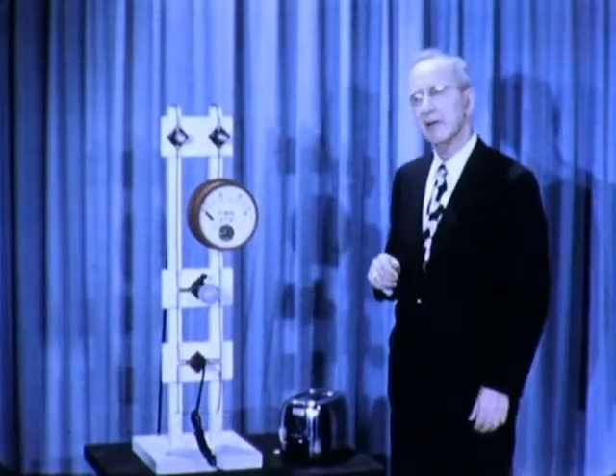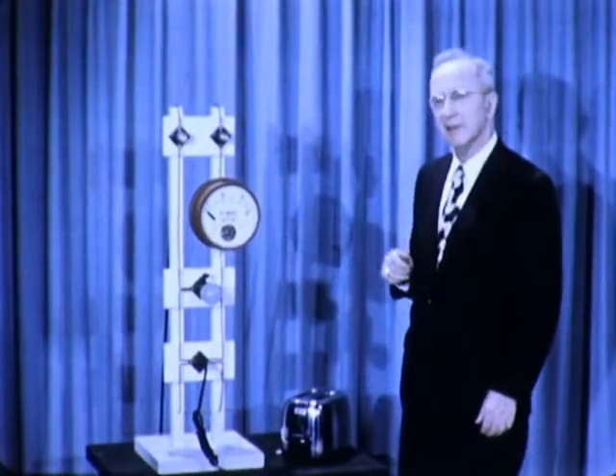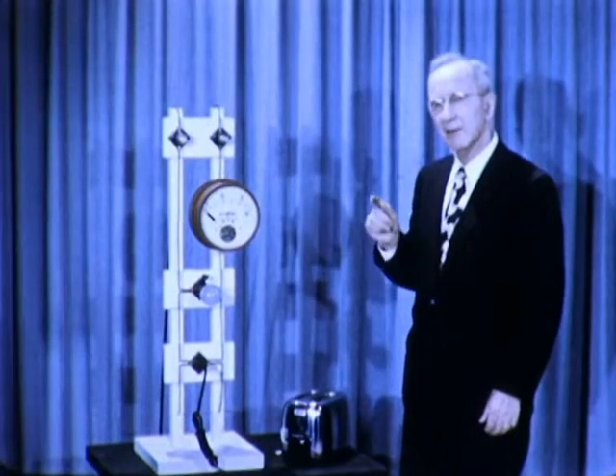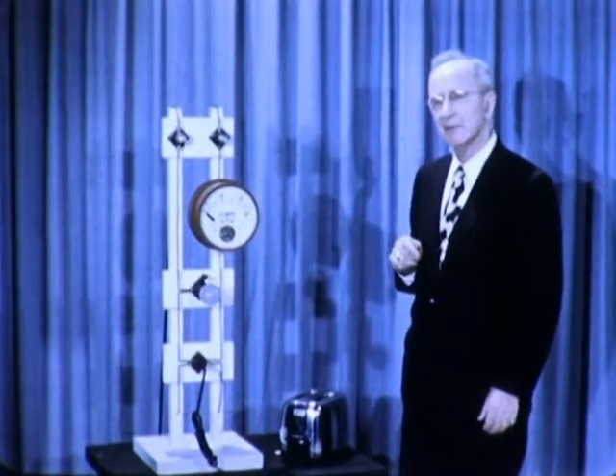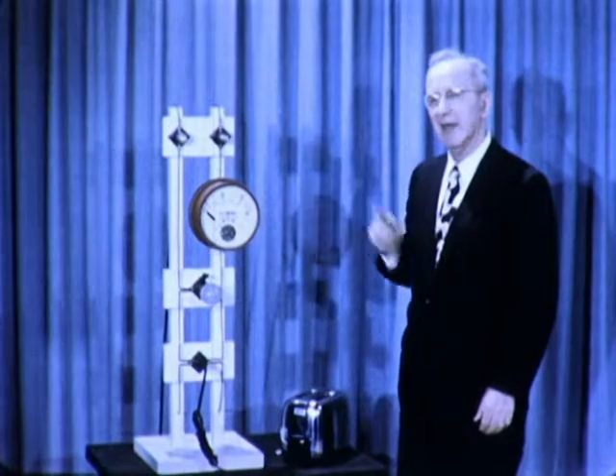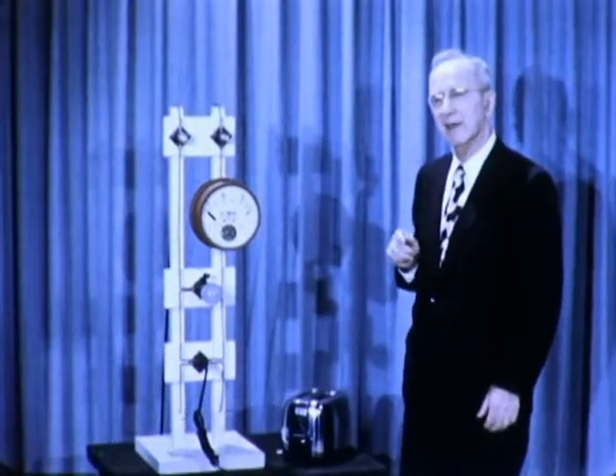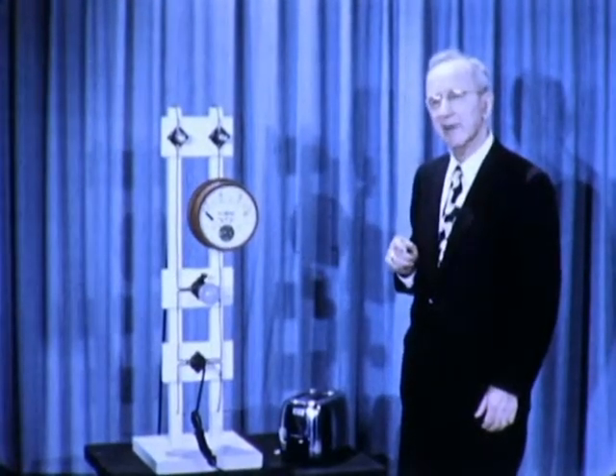This brings me to my point that adequate interrupting capacity is one of the most important things in electric service, because this may happen in any part of the system and may result in considerable damage. Now, when talking about protective devices, the most important question is: are they adequate or inadequate? Are they capable of interrupting the maximum amount of power that can be delivered under short-circuit conditions?